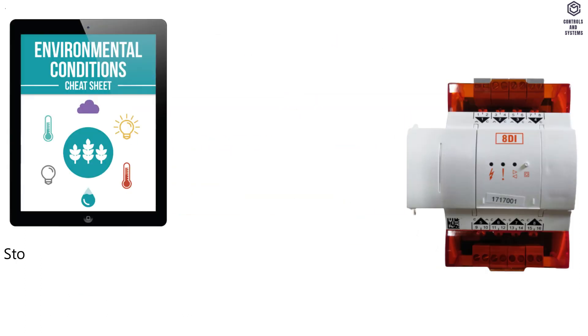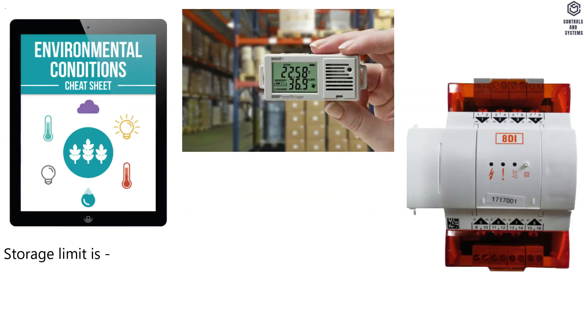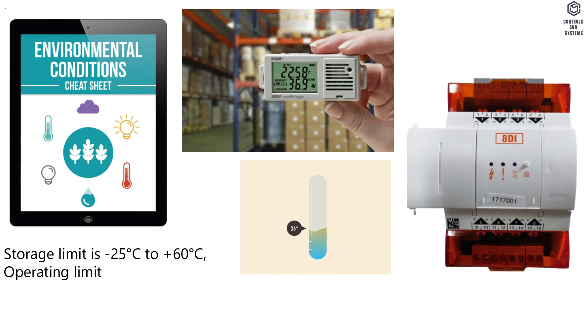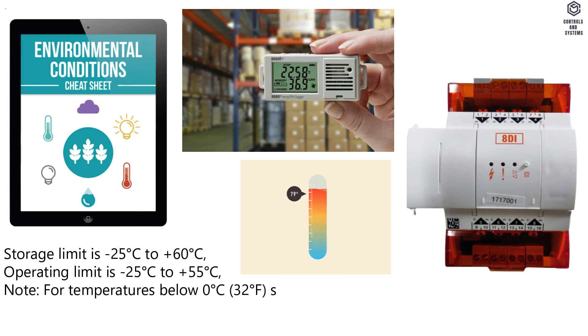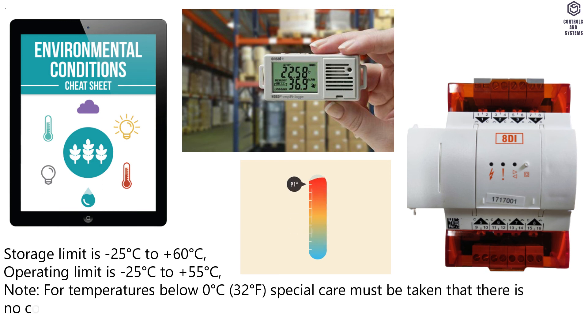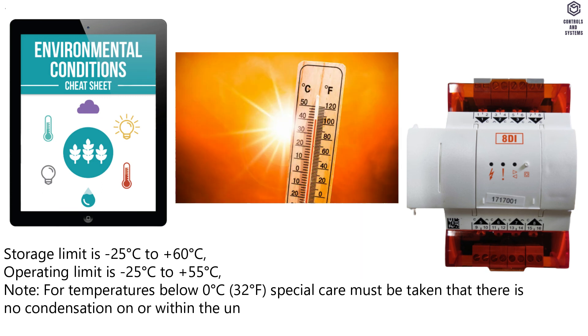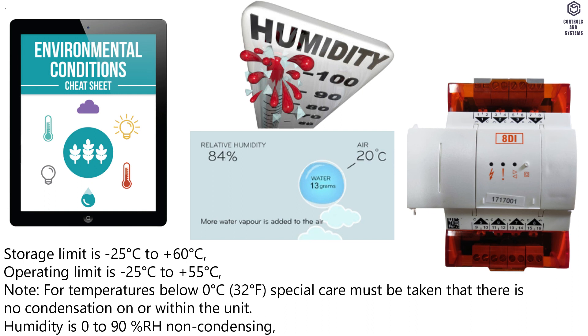Ambient limits: storage limit is -25°C to +60°C. Operating limit is -25°C to +55°C. Note: for temperatures below 0°C, special care must be taken that there is no condensation on or within the unit. Humidity is 0 to 90% RH non-condensing.